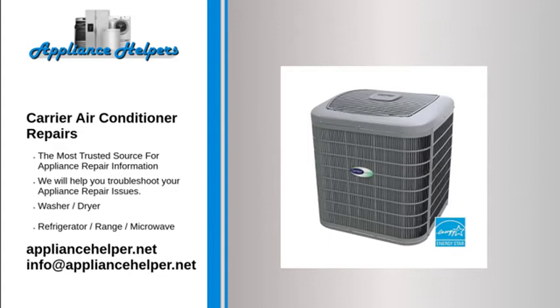Circuit breaker is tripped. If you are satisfied that the thermostat settings are correct, check your power supply. Your AC system runs on electricity, and there are typically 3 locations you can check to be sure the issue isn't with power to the system. First, locate your main breaker box panel and make sure the AC system circuit breaker hasn't been tripped. The outdoor unit typically takes 220 V power to operate and should be on its own circuit.